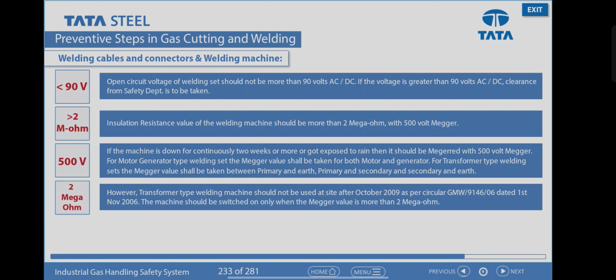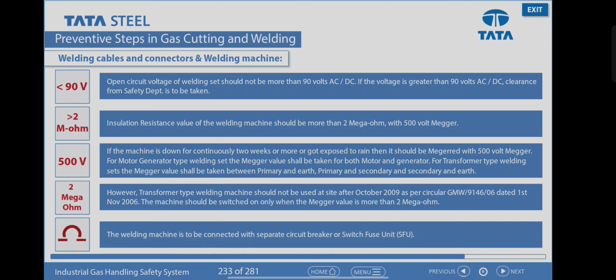However, transformer type welding machines should not be used at site after October 2009 as per Circular GMW/9146/06 dated November 1st, 2006. The machine should be switched on only when the megger value is more than 2 megaohm. The welding machine is to be connected with a separate circuit breaker or switch fuse unit, SFU.